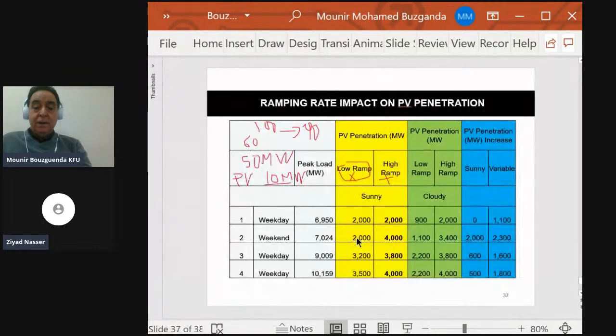This affected the penetration of the PV. Here you have a weekday, a flat load. Whether you have high ramp or low ramp, you still get the same number. On the weekend, with low ramping rate you got 2,000 megawatt, with high ramping rate you got 4,000 megawatt. That's an increase of 2,000.